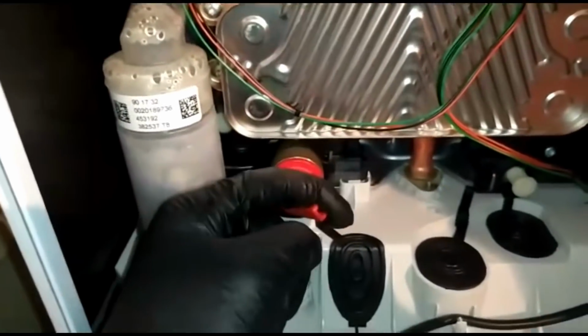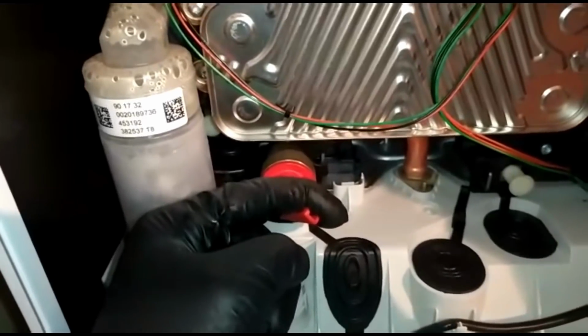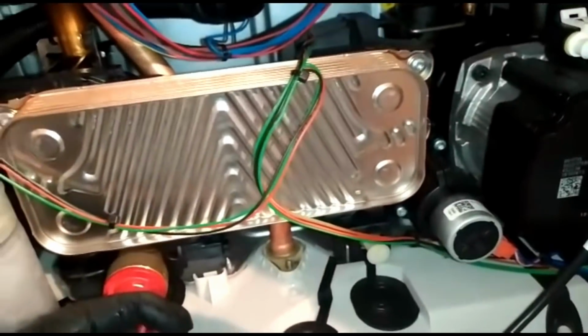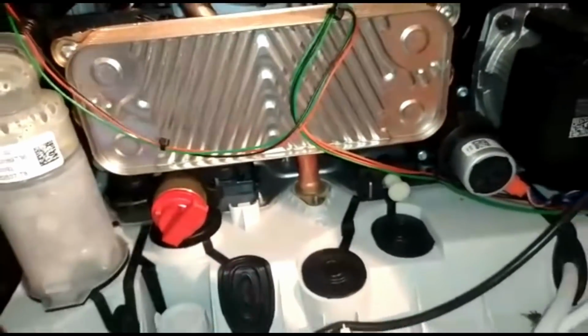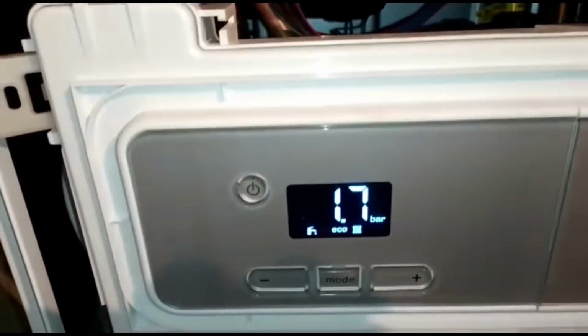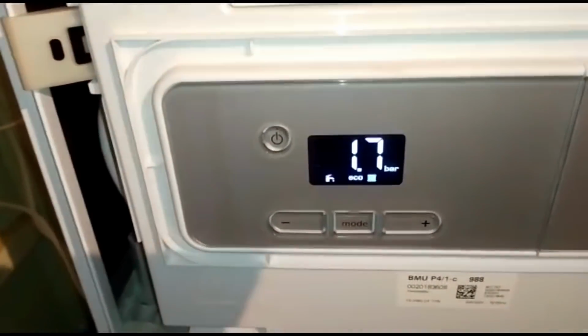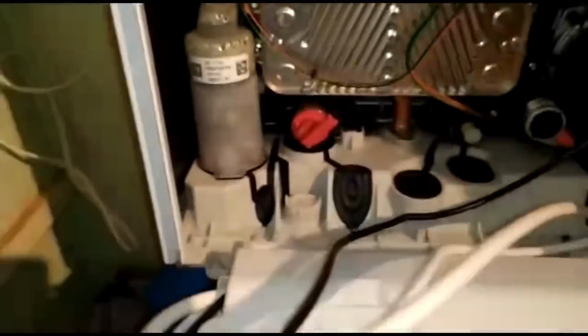Pressure relief valve fully open. Pump's trying to kick in, but the pressure relief valve is fully open on that one. The boiler is empty and yet it's showing 1.7. And I'm just going to power down the boiler.